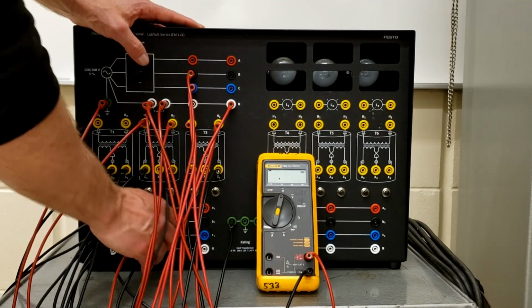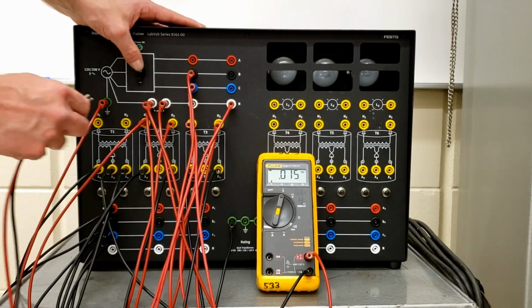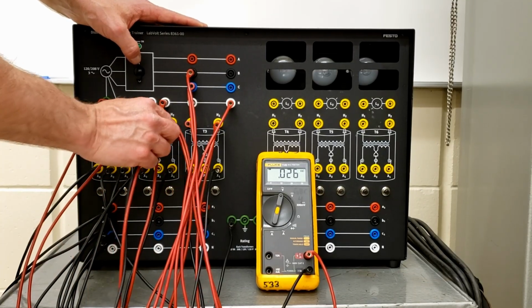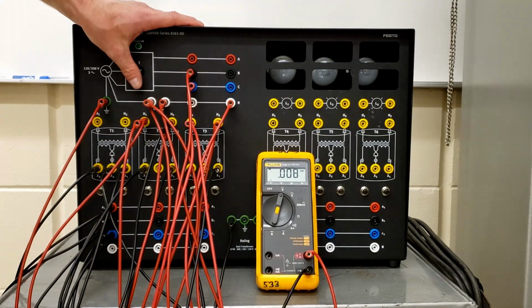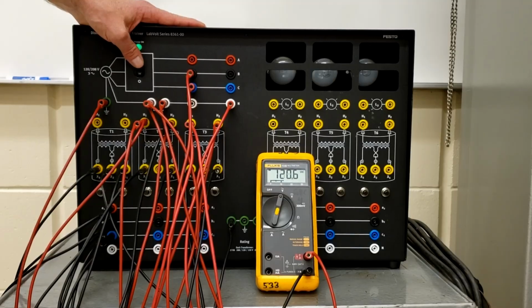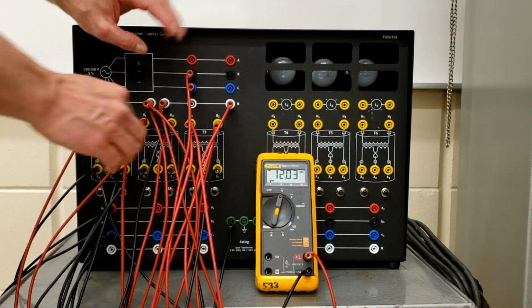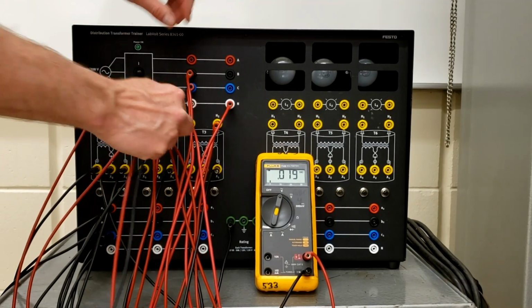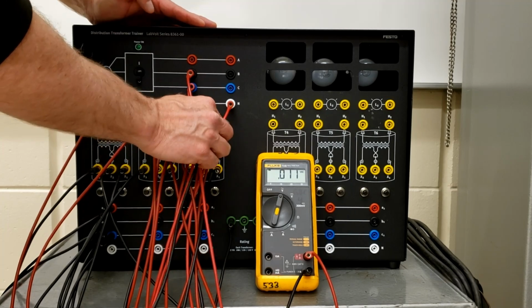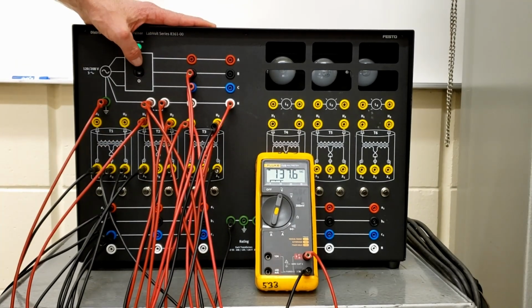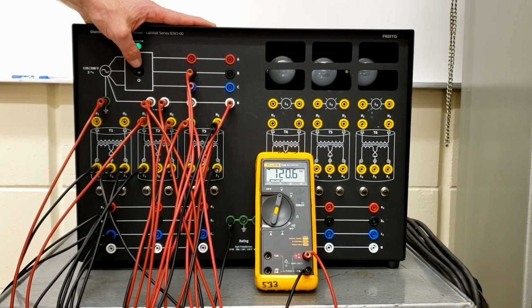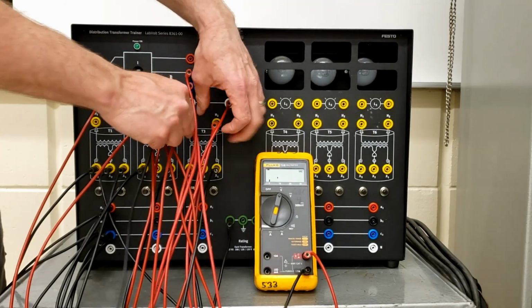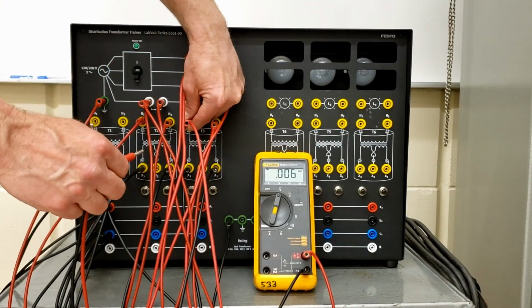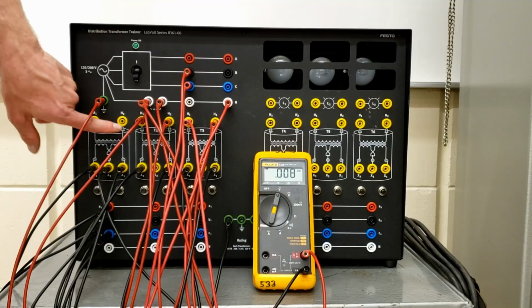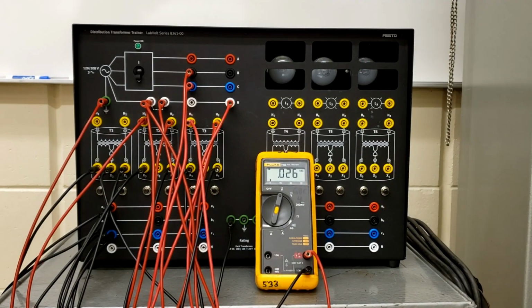Let's check our primary voltage here. So we're checking out the voltage between H1 and H2. This should still be 120. Okay, so still 120. And on this guy, we should still have 120 as well. Excellent. So small drop in voltage on the A and the B phase on the secondary side once we've opened that delta there. But aside from that, the C phase was identical.